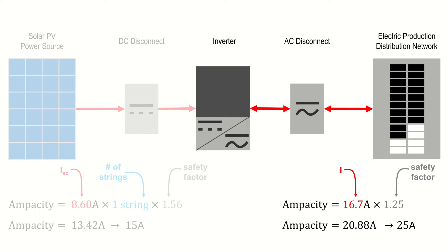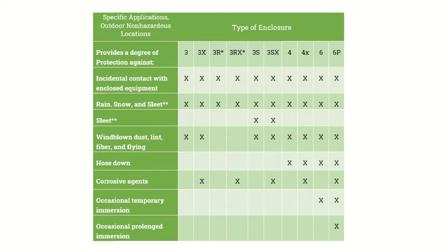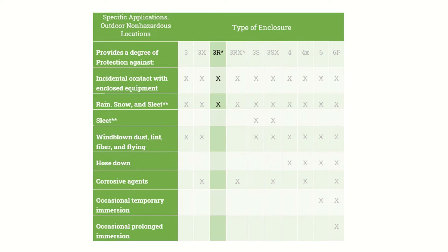You'll also need to consider the environmental conditions that the disconnect switch will be exposed to. The enclosure itself must be rated for the environment that it's installed in. Since these interconnections are typically installed outside on exterior walls near the electric meter, a NEMA 3R enclosure will usually suffice. Type 3R enclosures protect against falling rain, sleet, snow, and external ice formation. You can review the 2020 NEC 705.11 for more details.